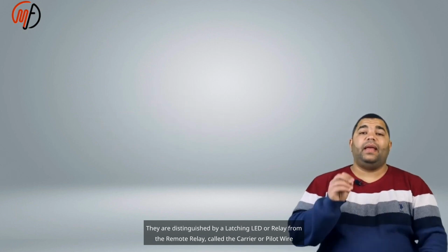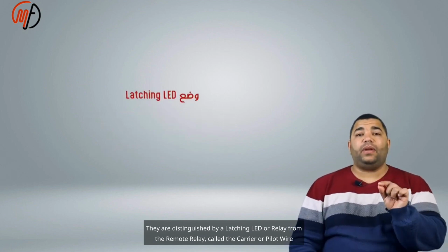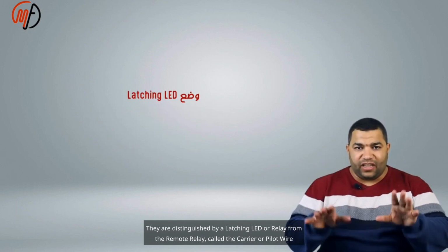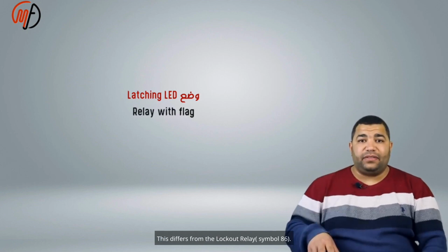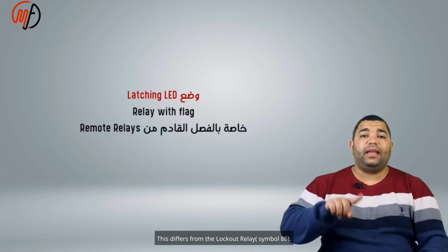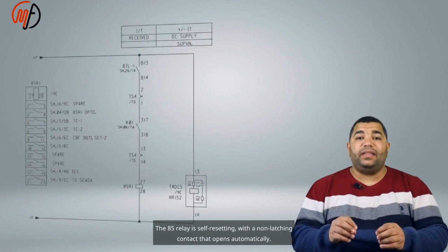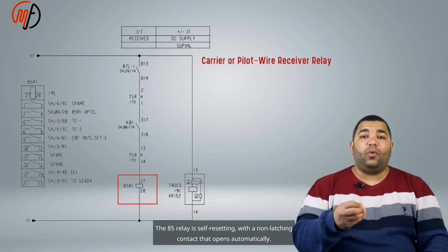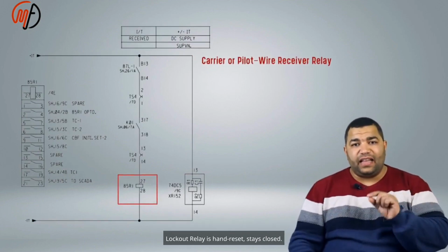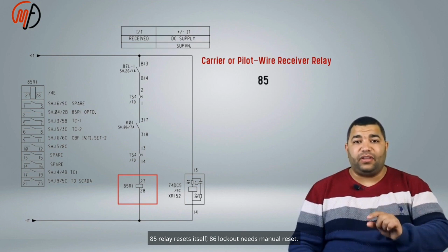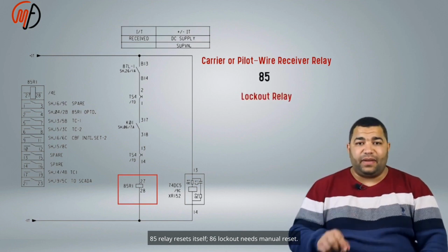They are distinguished by a latching LED or relay from the remote relay, called the carrier or pilot wire receiver relay, symbol 85. This differs from the lockout relay, symbol 86. The 85 relay is self-resetting, with a non-latching contact that opens automatically. Lockout relay is hand reset, stays closed. 85 relay resets itself, 86 lockout needs manual reset.